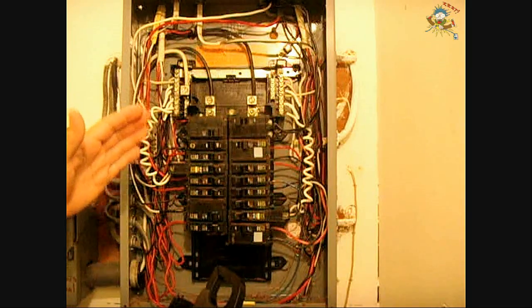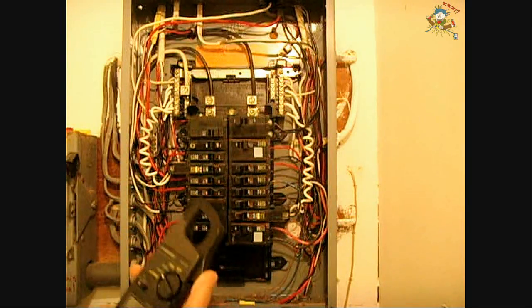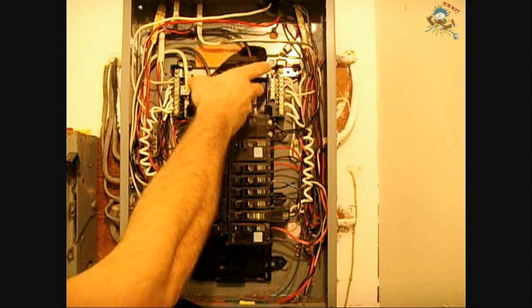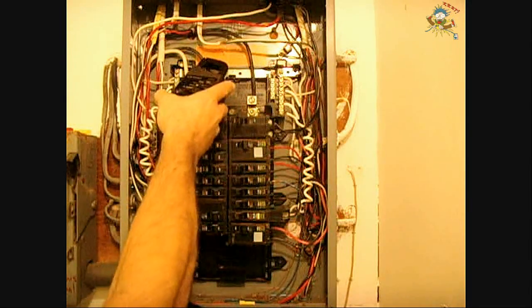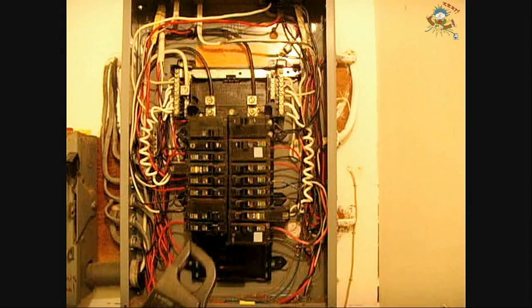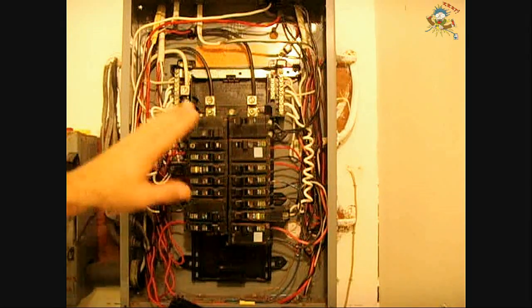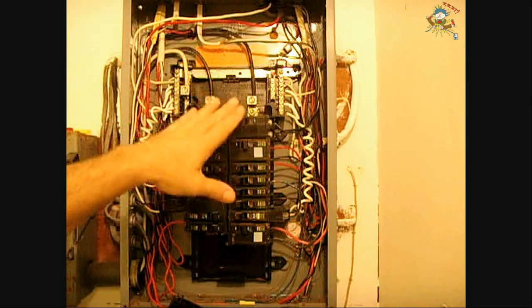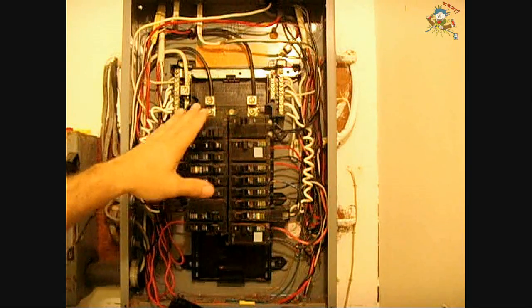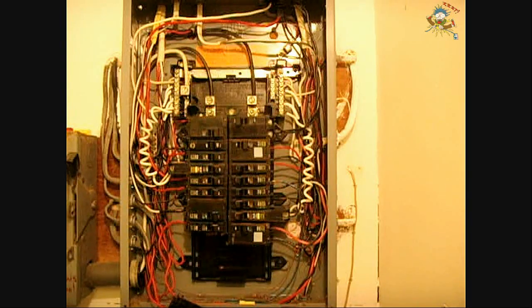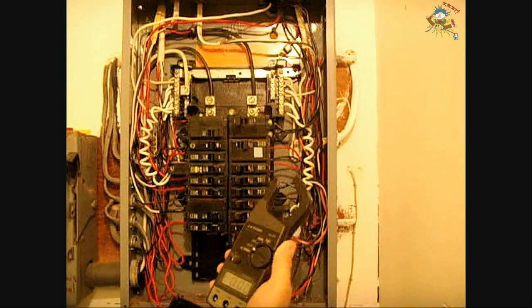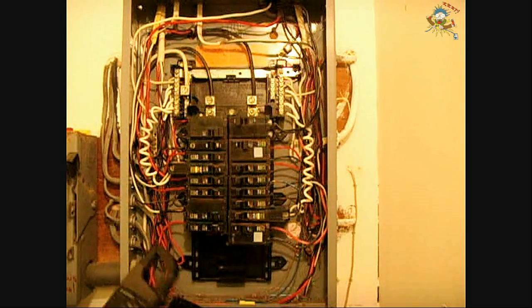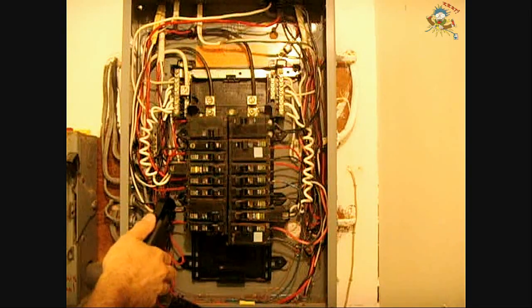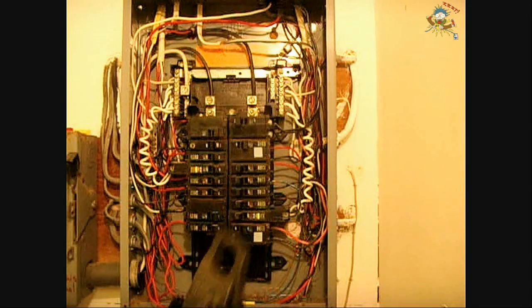You would have everything running like it would normally be running, and then you could take a measurement with your air conditioning going or anything else and compare the readings on the two wires. You want to have them very close in the amount of load on each one. You don't want to have one with 80 amps and one with 20, so you would want to balance things out. This is also very useful for measuring the current flowing through wires. If I wanted to check the water heater current, I could do it from here as well. Very handy tool.